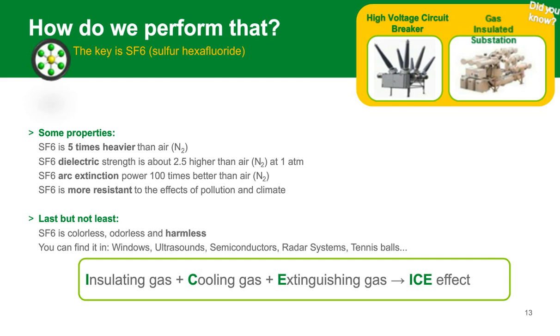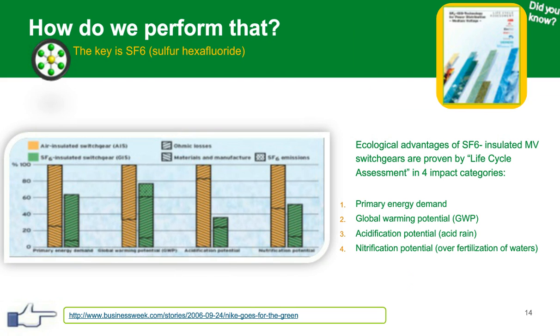Now, a key point with SF6, and probably what most of you on the phone are familiar with, is that it is a greenhouse gas. It has a much higher global warming potential than carbon dioxide. And so that's why there are some careful steps being taken to ensure that we limit the amount of leakage and reduce the total amount of gas needed in medium voltage switchgear.